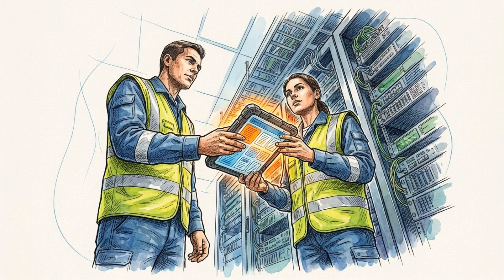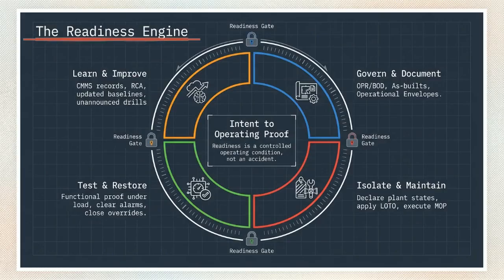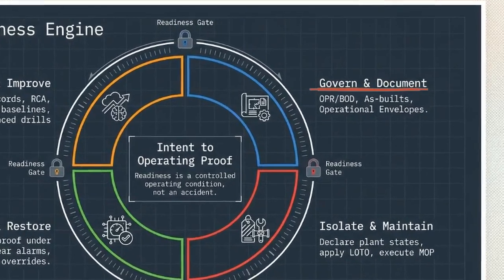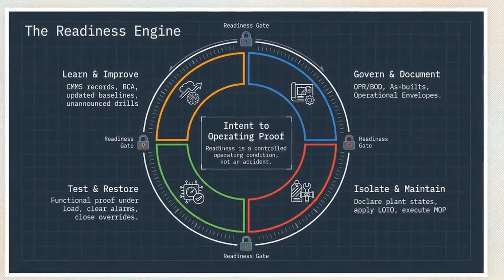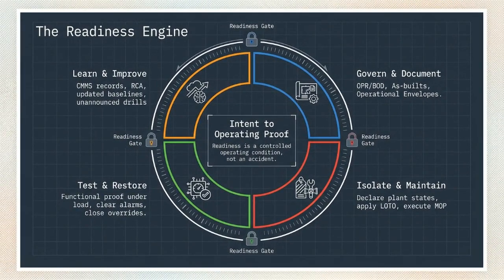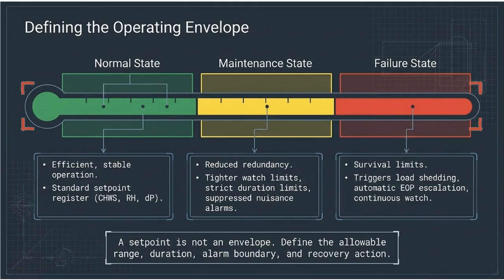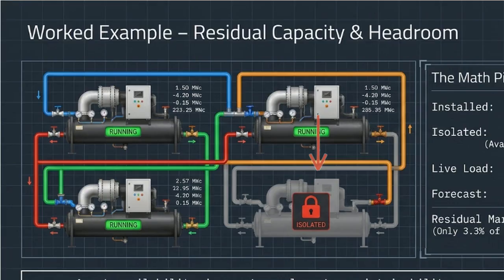This circular diagram illustrates the readiness engine. Readiness is not a static achievement. It is a continuous, controlled operating cycle moving through phases of governing documentation, isolation of assets, rigorous testing under load, and continuous learning. This thermometer gauge defines the operating envelope. An envelope is a combination of allowable ranges, duration limits, alarm boundaries, and specific recovery actions across normal, maintenance, and failure states. Having physical assets installed does not guarantee system maintainability.